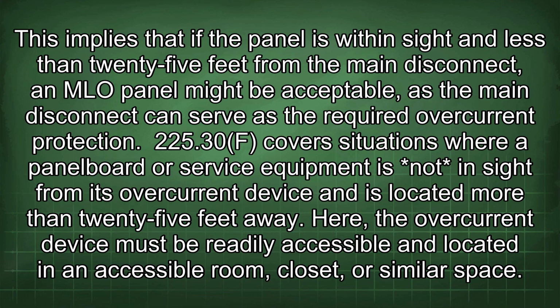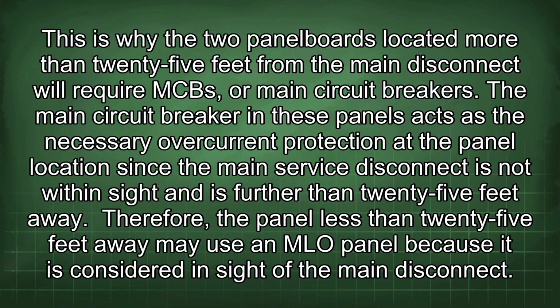225.30f covers situations where a panel board or service equipment is not in sight from its overcurrent device and is located more than 25 feet away. Here, the overcurrent device must be readily accessible and located in an accessible room, closet, or similar space. This is why the 2 panel boards located more than 25 feet from the main disconnect will require MCB, or main circuit breakers. The main circuit breaker in these panels acts as the necessary overcurrent protection at the panel location, since the main service disconnect is not within sight and is further than 25 feet away.